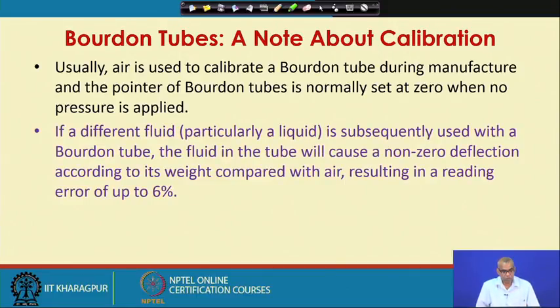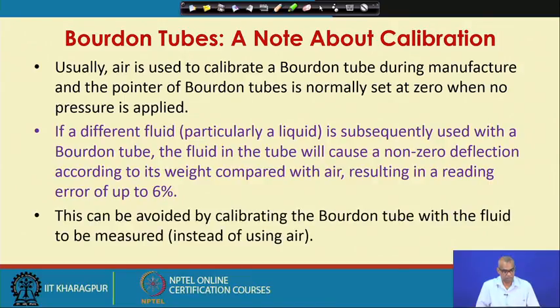If a different fluid, particularly liquid, is subsequently used with a Bourdon tube, the fluid in the tube will cause a non-zero deflection according to its weight compared with air, resulting in a reading error of up to 6%. This can be avoided by calibrating the Bourdon tube with the fluid to be measured instead of using air.